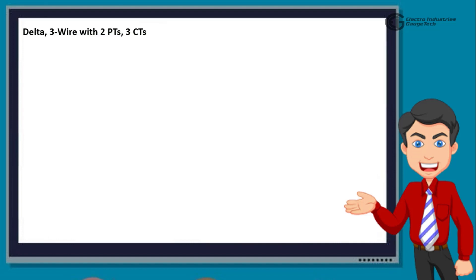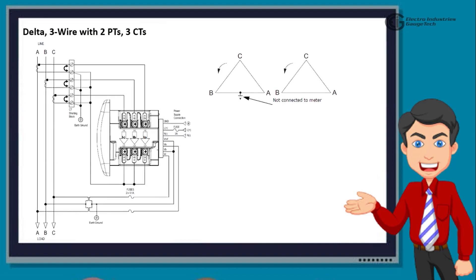Next, we move to Delta, 3 wire with 2 PTs, and 3 CTs. This diagram shows 3 phase, 3 wire Delta system with 2 potential and 3 current transformers. When using this wiring, select 2 CT-Delta from the Shark Meter's front panel display.